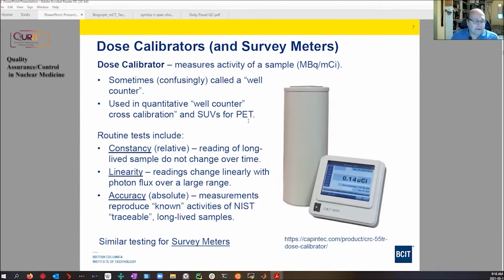I want to start, though, with a very humble instrument, the dose calibrator. And what applies to this also applies to survey meters. I won't ask you, but some of you may have run into using a dose calibrator. It's a device which measures, when we put a vial in with a sample of radioactivity in, it will give a measure of what that activity in the sample is. So I hope you can see my little cursor here. This cylindrical object is hollow inside. It's an ionization chamber.